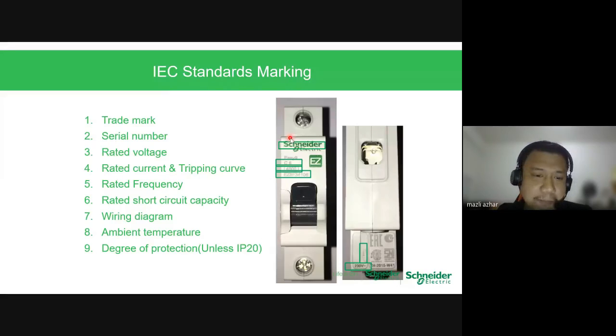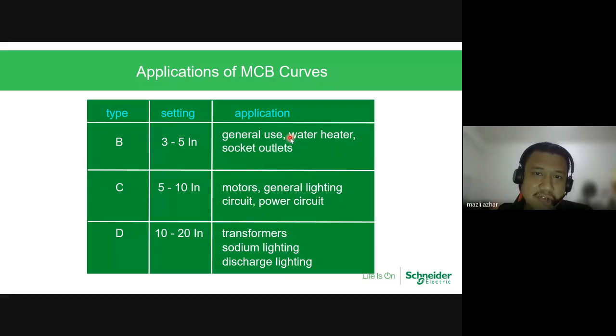Okay, so application of MCB curve B, C, and D. Why are these things important? Have you guys ever heard about starting current? All right, so take for example motors. Maybe the rated current is 32 amps, but the starting current may go to 5 times, 6 times, 7 times, depending on the motor itself.